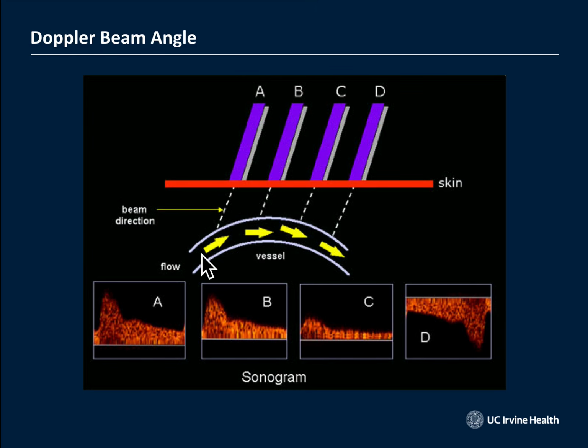And as the flow is coming towards and then away from the transducer, in this example of pulsed wave Doppler images, you can see as it's coming towards the probe, the beam angle is constantly changing. Where it's more parallel, you get a much better representation of the actual velocity of the flow. And when it gets more perpendicular, it almost seems like the velocity is dropping. It's not, it's just not as accurate.